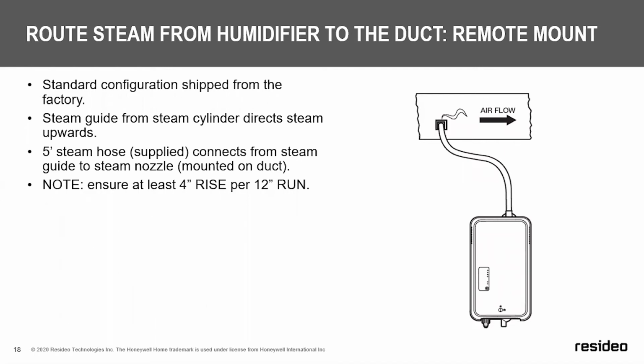Ensuring that where the nozzle is installed, you have at least 4 inches of rise. That means 4 inches before you have the ceiling of your ductwork, and 12 inches of run or throw, which is the amount of space needed for that steam to get into the ductwork and be absorbed by the airflow before it has a chance to hit the walls of the ductwork and potentially condensate.